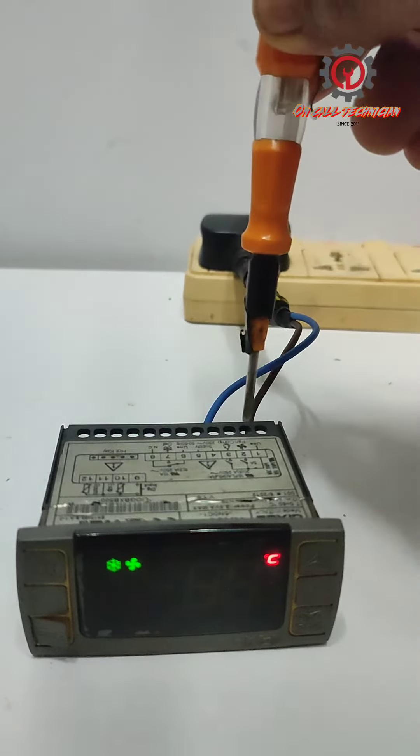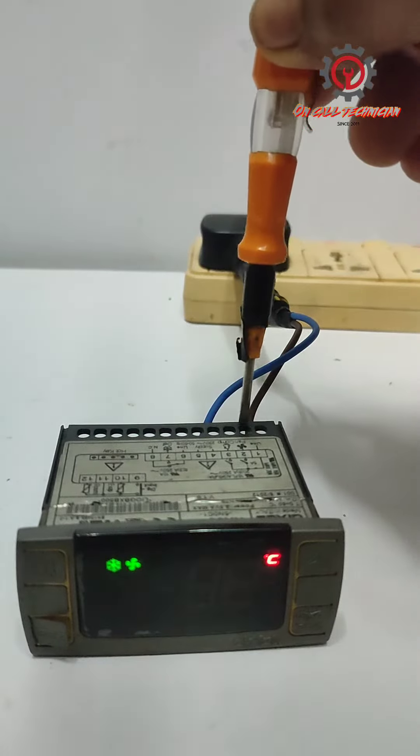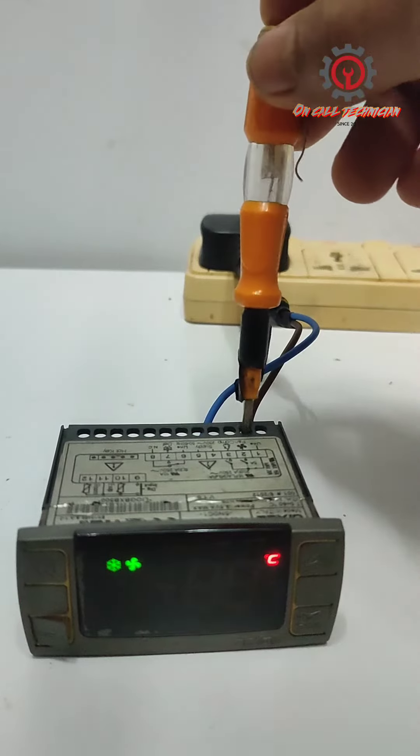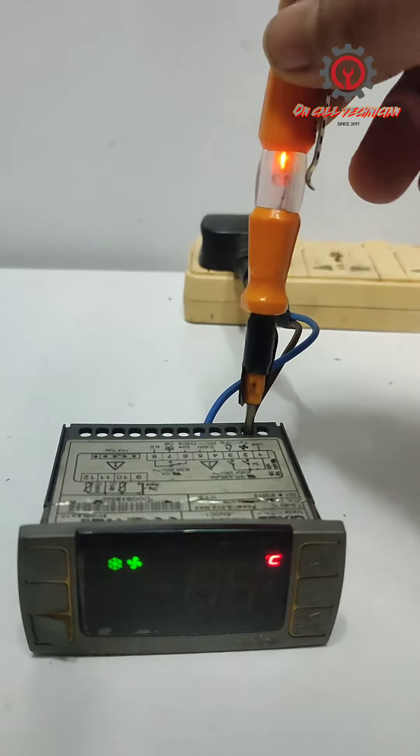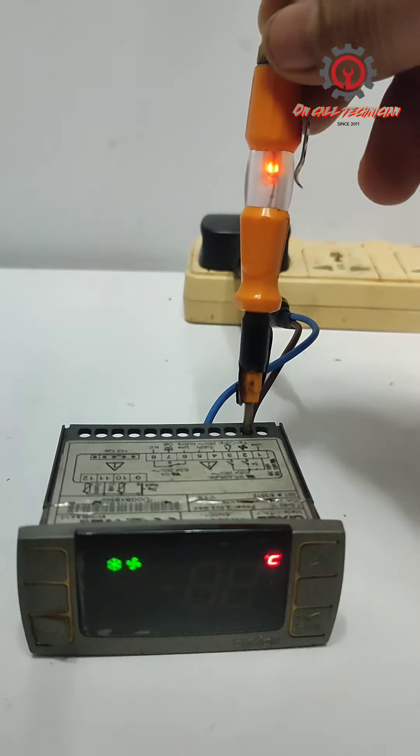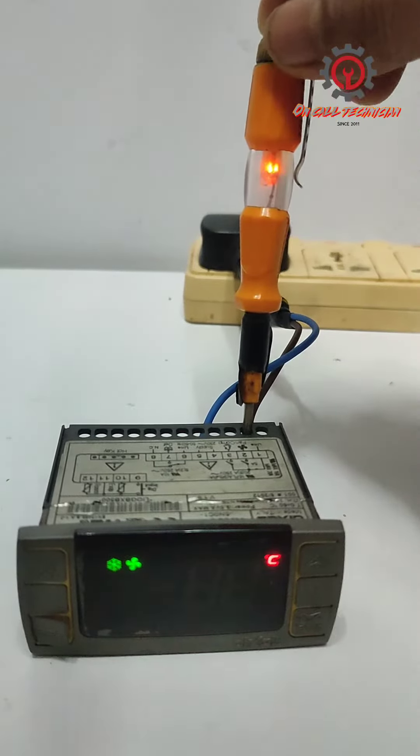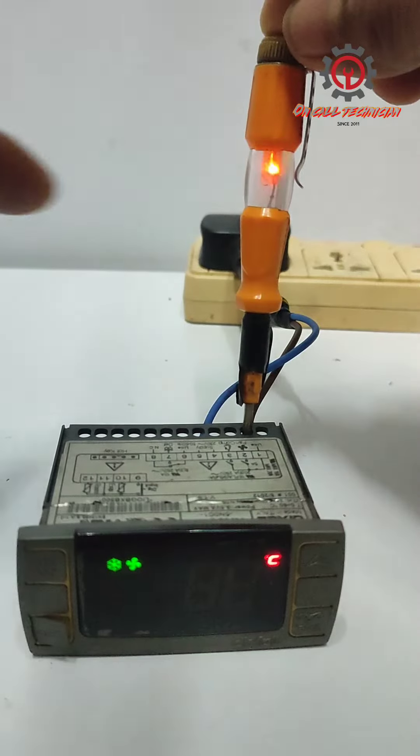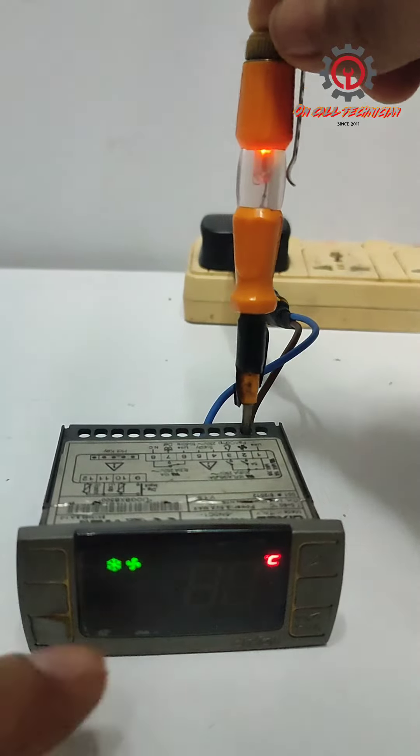Terminal number two is for the fan. Take a look, the test pen lights up, meaning there is output voltage for the evaporator fan.